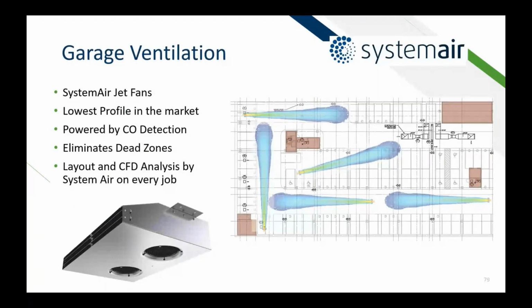Most multifamily construction will typically require or involve garage ventilation. I'm still surprised to this day to see how many engineers use duct systems throughout a garage, but that is by far the least effective way to do this, and it's not even a very cost competitive way to do it. These jet fans are by far the best way to eliminate dead zones in your garage, and they basically sit up in the garage.